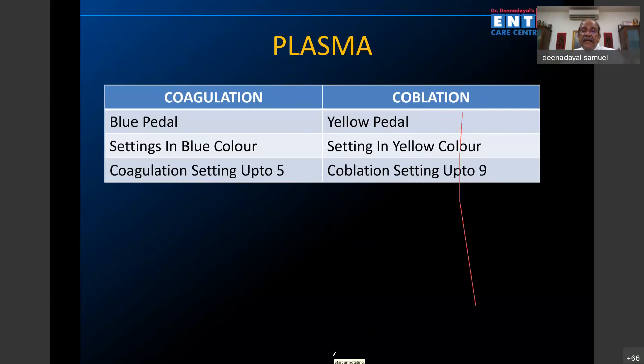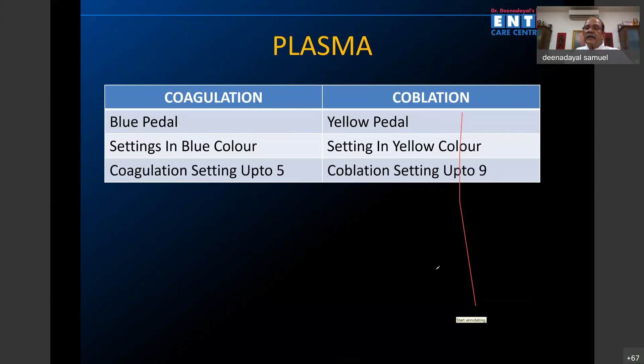The coagulation setting has a maximum of five, and the yellow coblation pedal can go up to nine.